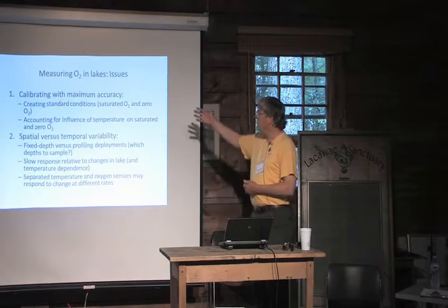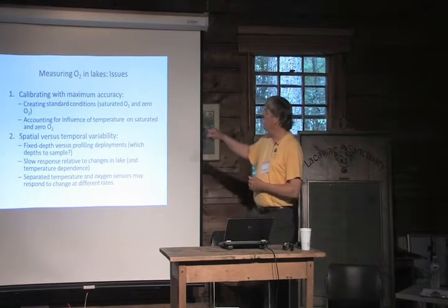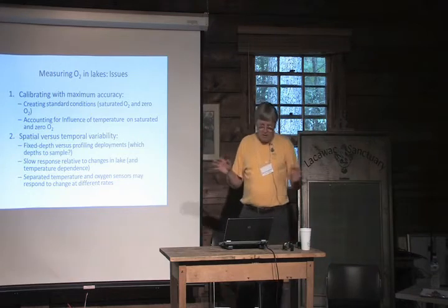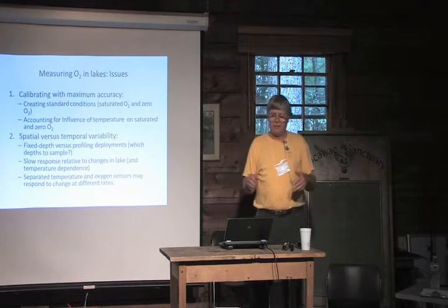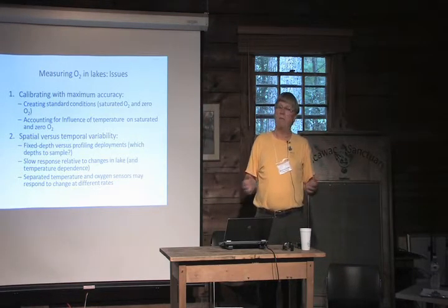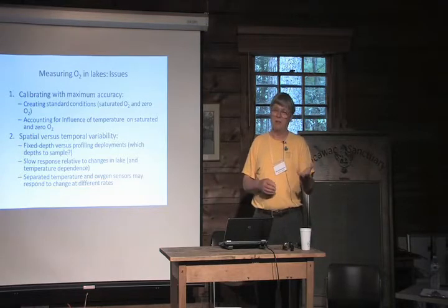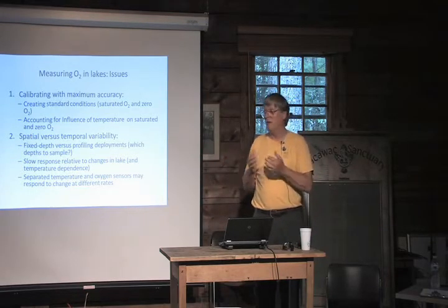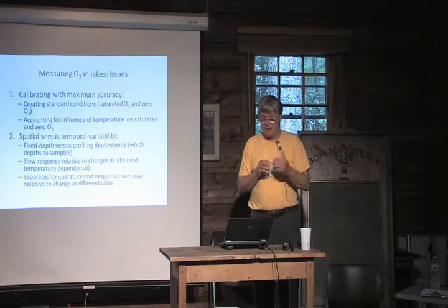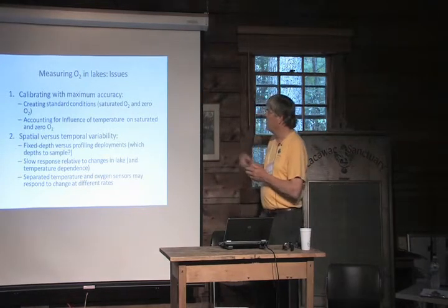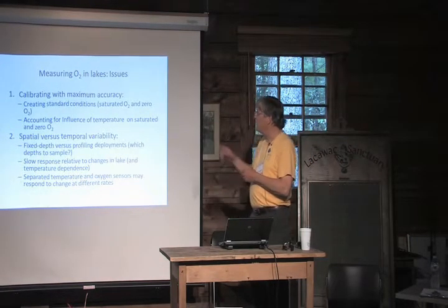So there's calibration issues. And finally, in all these oxygen sensors, they have a signal at zero oxygen that's not zero, and you need to account for that for accurate readings, especially if you're doing something like the Emerald Bay example where you want to calculate how close to zero you get. So I'll talk about examples of that in a few minutes.